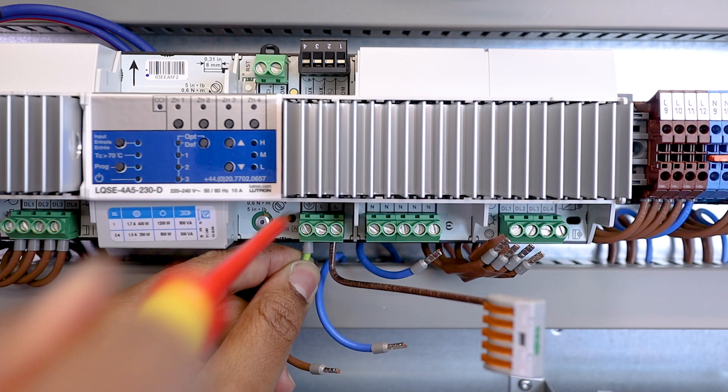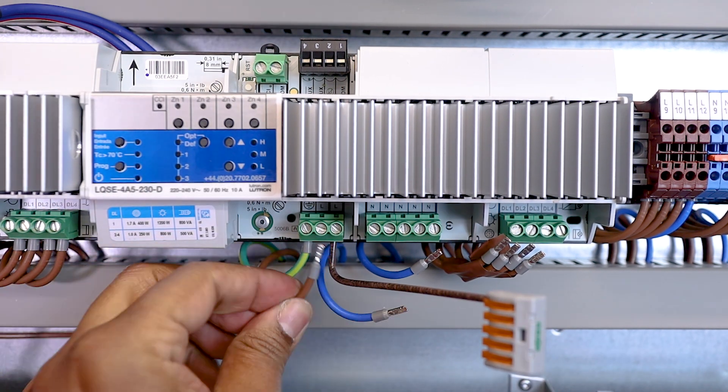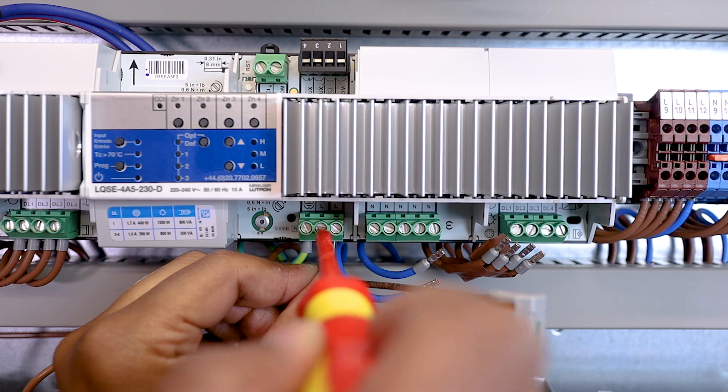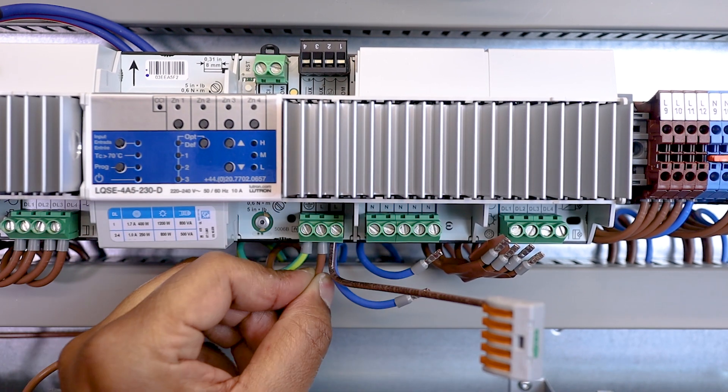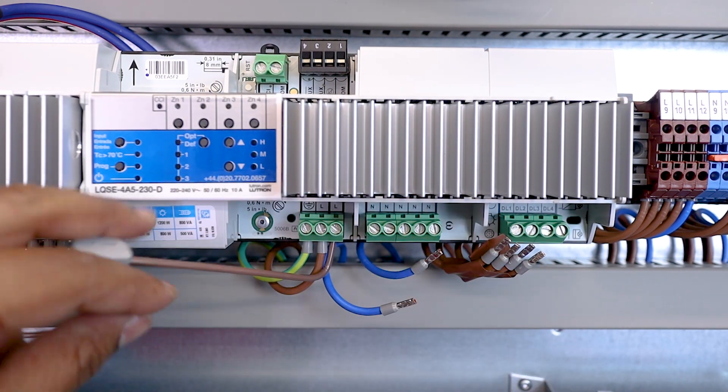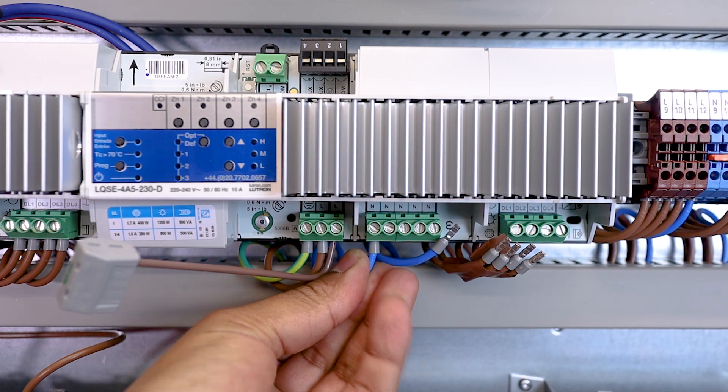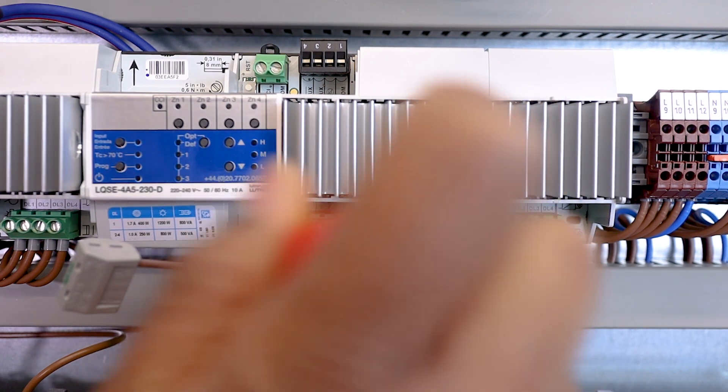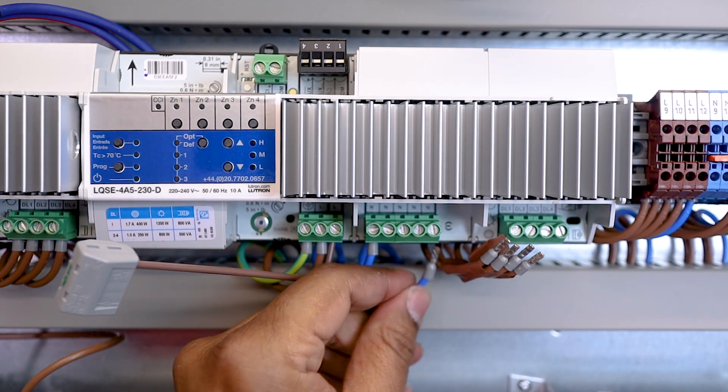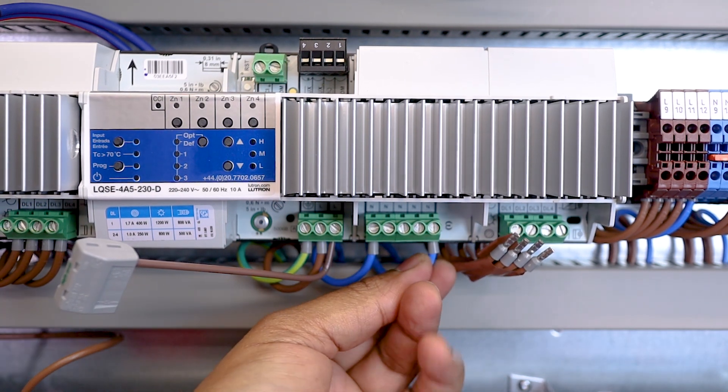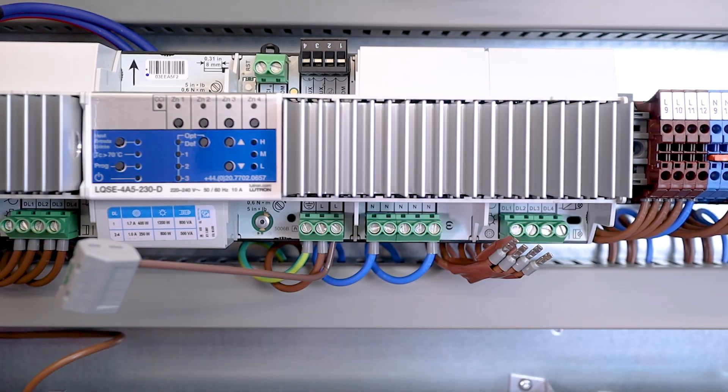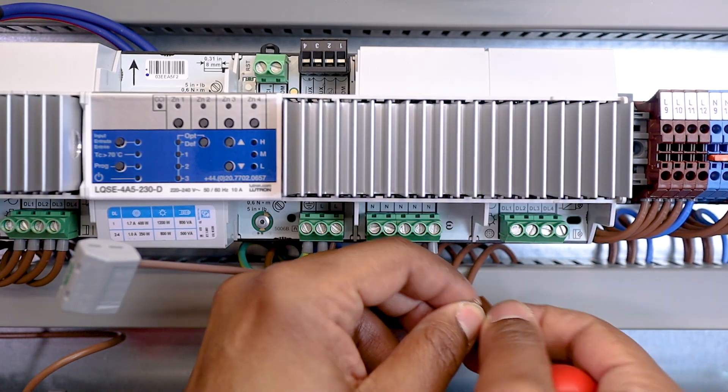Okay, so, I wire the GND, then I wire the Live coming from the breaker to power the module. I wire the Neutral also coming from the breaker, and the second blue cable here is the same Neutral that goes back to the general terminal blocks that will fit the lighting circuits.